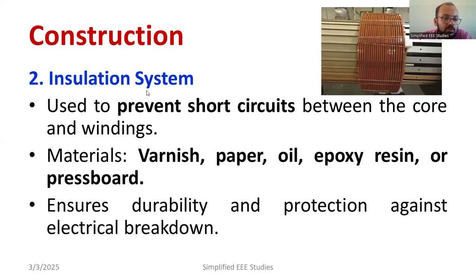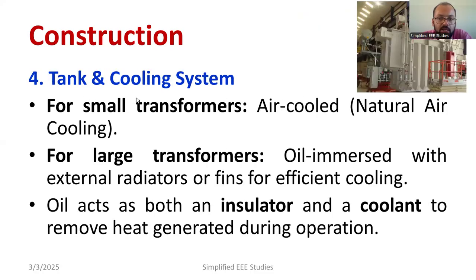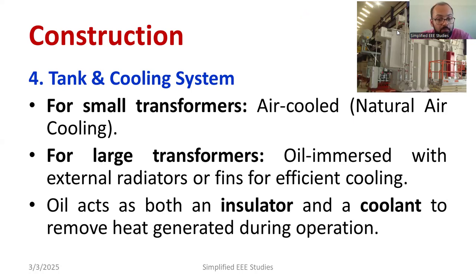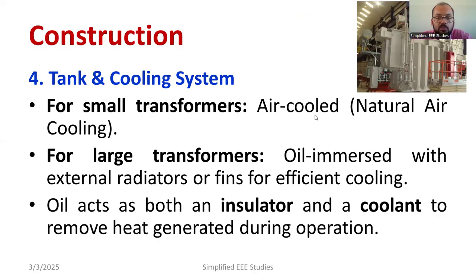If I talk about the transformer tank and cooling system, for small transformers, air cooling is more than sufficient. But for large, high-power transformers, the concentration of heat is very high and air-based cooling is not sufficient, so we go for an oil-based transformer cooling system.